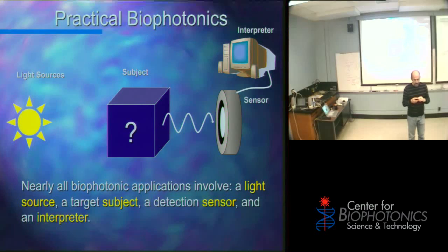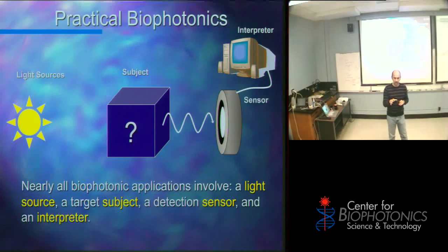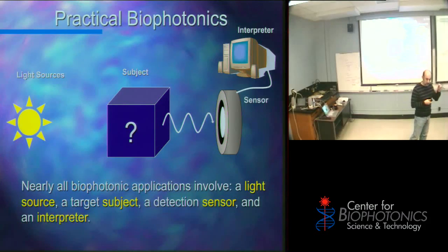Now, this is actually two different colors. There's red that you can see, and there's a near infrared, just like the TV remote control. Later on in this quarter, you'll get to actually see that because we'll have instruments that can detect that. And we'll see things that your eyes can't see. We'll see that there's actually two wavelengths here, and that the way this thing works, it turns on the red, turns it off, turns on the near infrared, turns it off, has nothing, and then starts the cycle again. It does that cycle about 120 times a second. So it does it very quickly, okay? And because of variations in your blood oxygen, in your breaths, between your heartbeats, it can figure out your heart rate too, okay? That's how this thing works.